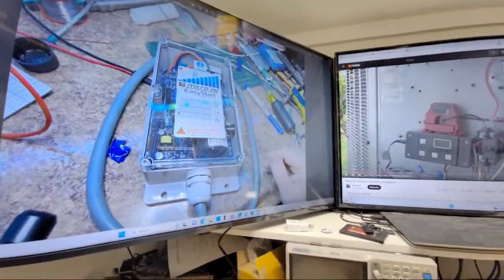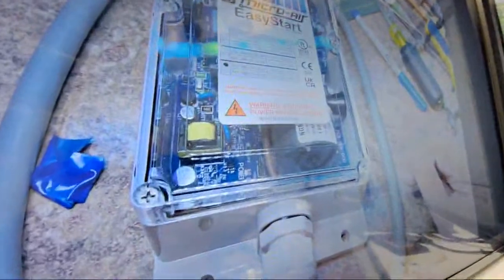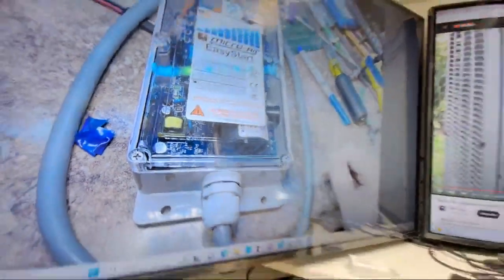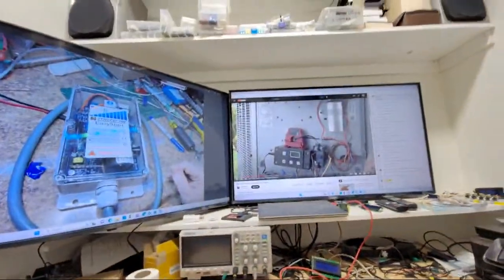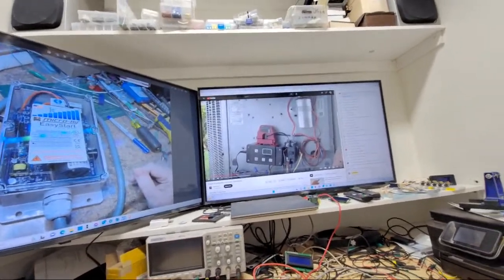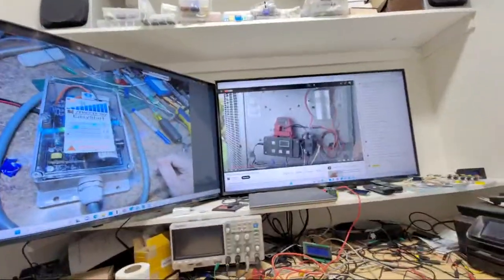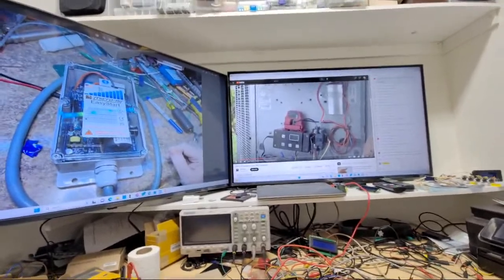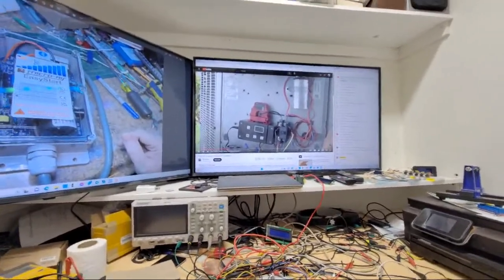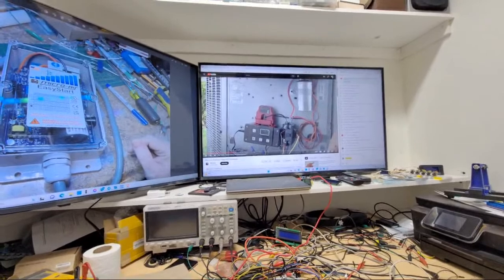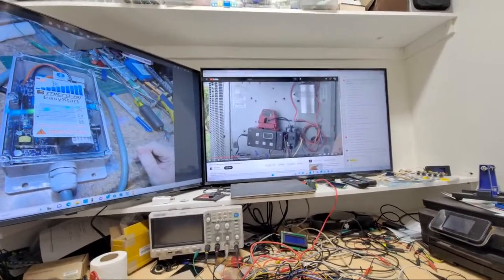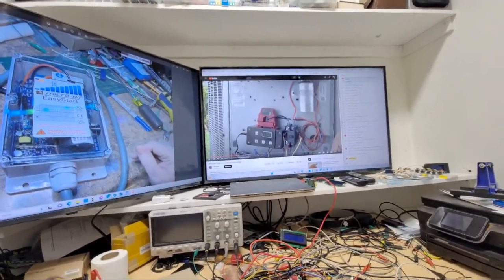So we're talking, I go, I see a start capacitor in there. If it was like a variable frequency drive type thing, they're not going to use that, they're just going to ramp up the frequency or something. I don't think you'd be able to keep that in there. But some people were thinking that it is, and then I looked at the HVAC Talk forum, and some people thought there might have been a real soft start or whatever.